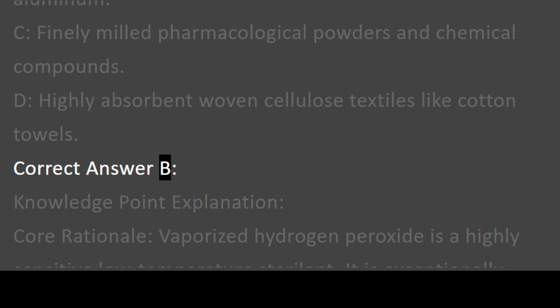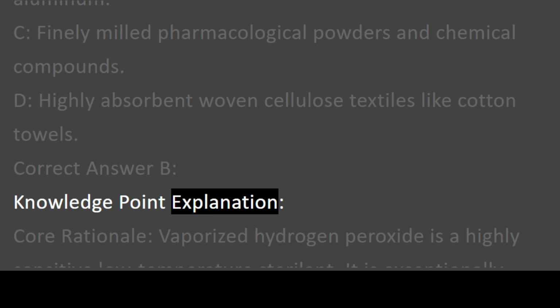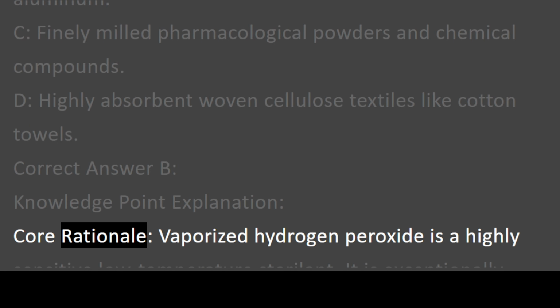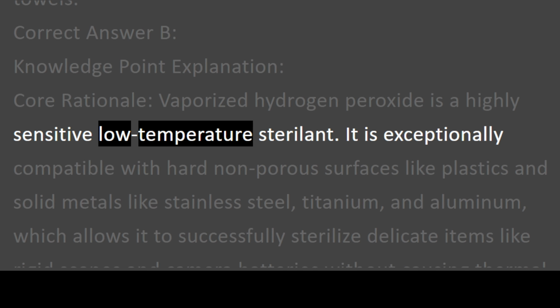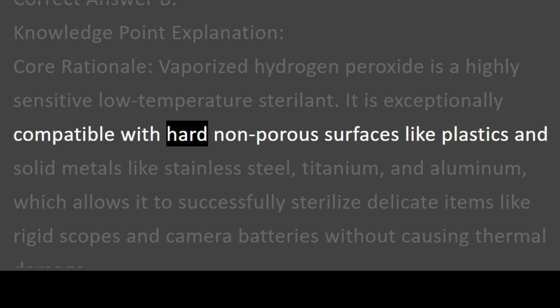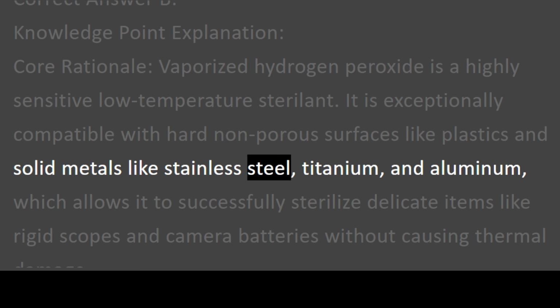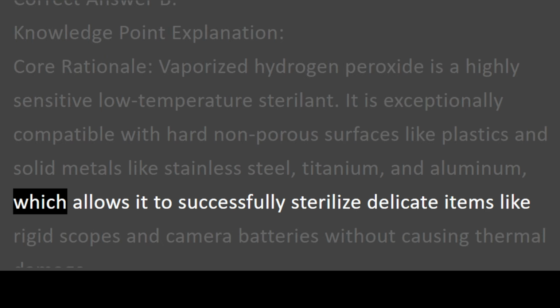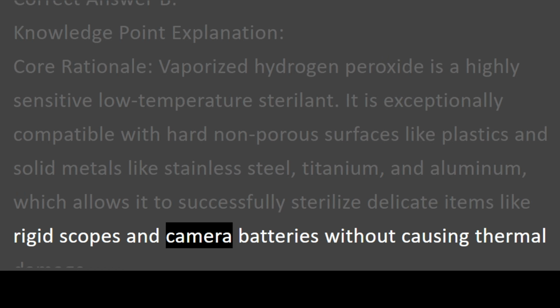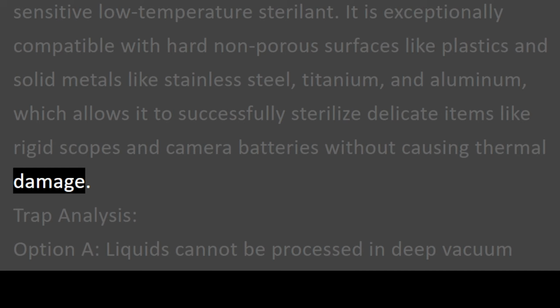Correct answer B. Knowledge point explanation. Core rationale. Vaporized hydrogen peroxide is a highly sensitive low-temperature sterilant. It is exceptionally compatible with hard non-porous surfaces like plastics and solid metals like stainless steel, titanium, and aluminum, which allows it to successfully sterilize delicate items like rigid scopes and camera batteries without causing thermal damage.